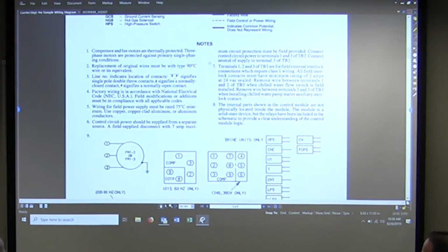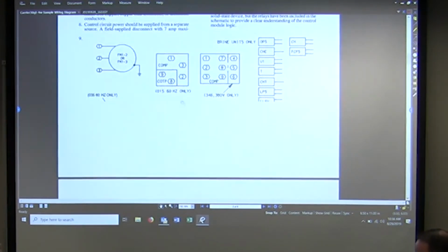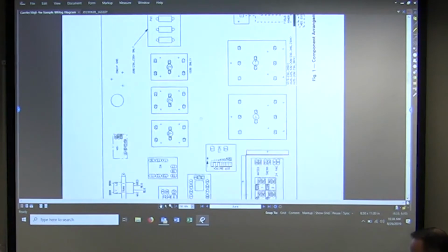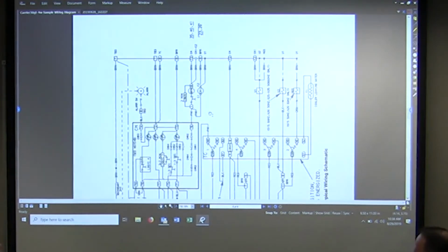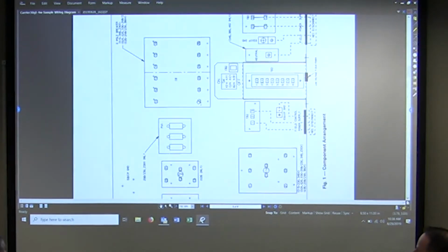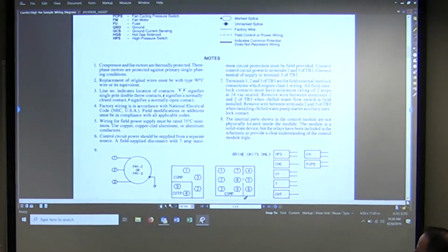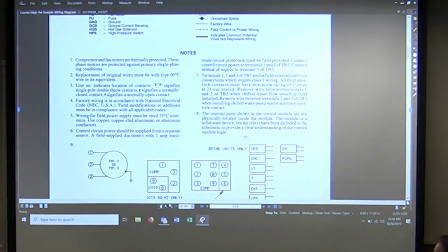And there's some notes. So note 8 has to do with page 5. Let me get back to 5 and just show you. I'm not going to twist my view, but it's this controller piece right here. So if we go back to note 8, it says the internal parts shown in the control module are not physically located in this module. The module is solid state, but the relays have been included in the schematic to provide a clear understanding of the control module logic. Okay, so everything in that box is integrated.